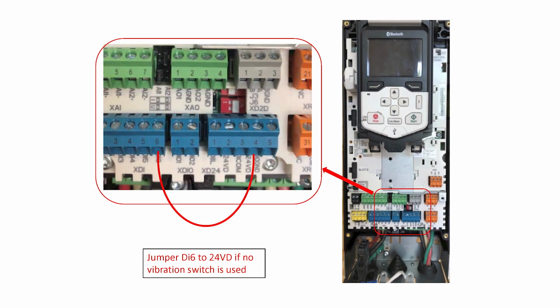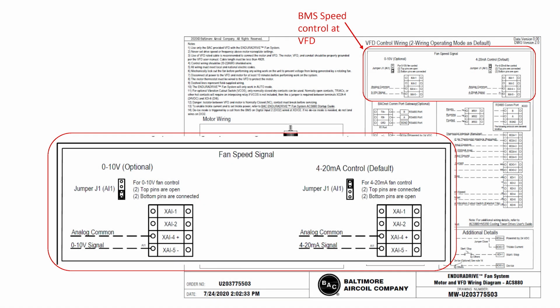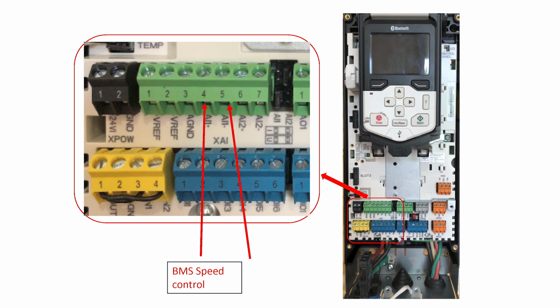If you are not using a tower vibration switch, you will need to insert a jumper wire between VFD terminals XDI6, labeled as DI6, and XD24-4, labeled as 24VD. BMS wiring. Now that you have confirmed proper wiring of the optional vibration switch, it's time to check the BMS wiring. Depending on your BMS system, your speed command will be either 0 to 10 volt signal or 4 to 20 milliamp signal.